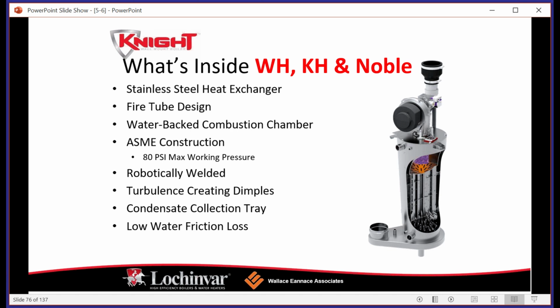You can see we've got our blower up on the top here. We've got our fresh air coming in from, again, outside or room air, pulling our gas through, creating the air fuel mixture, creating that flame, pushing that energy down through the heat exchangers, through the fire tube heat exchangers. As that flame or that heat moves through those baffles, those tubes, it comes in through the top in a flame state, right? And as it moves down through, you've got your cooler water coming in through the return, you've got your heated water going out the top. So what's happening is the cooler water, again, ideally you're going to want to be in about the 130-degree range, cooler the better, is changing the flame's state inside the heat exchanger, okay? So again, it comes in as a flame, it comes out as condensate, it gets collected in that tray and sent on its way.